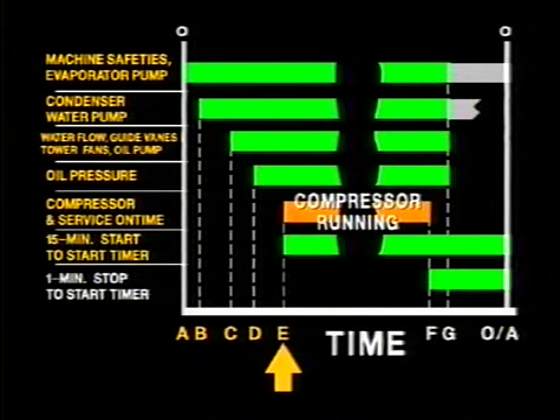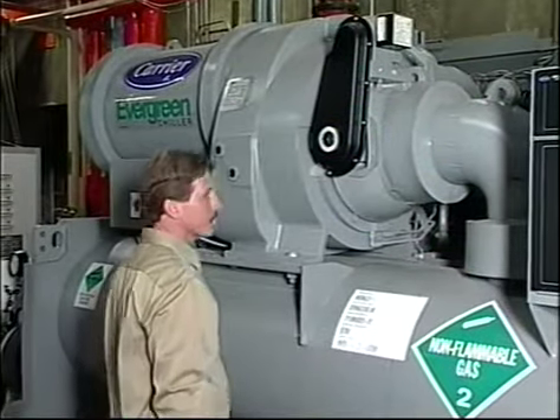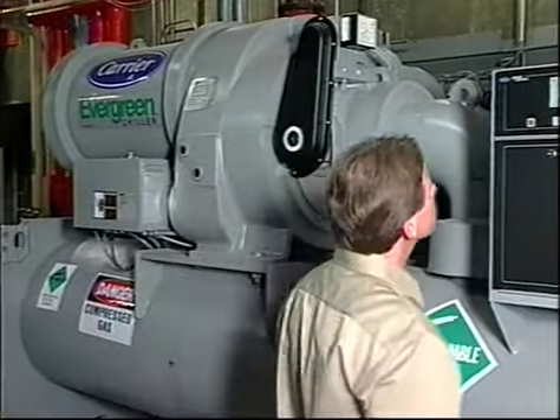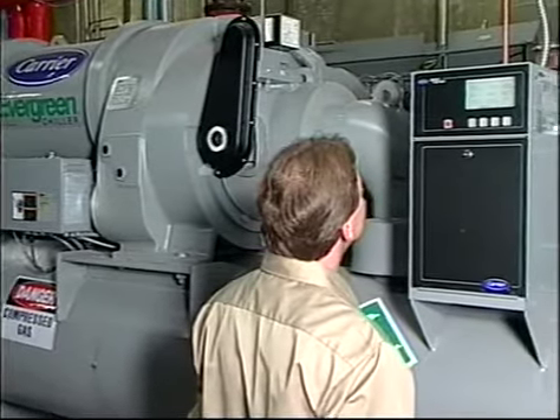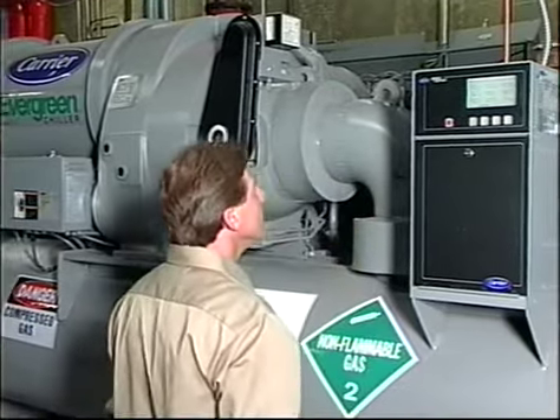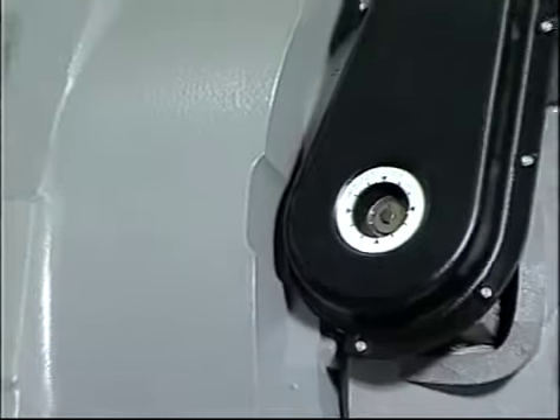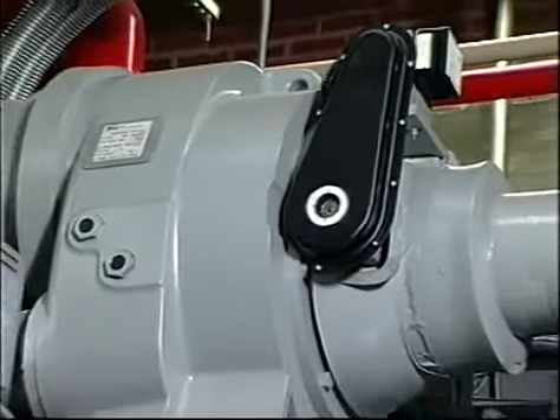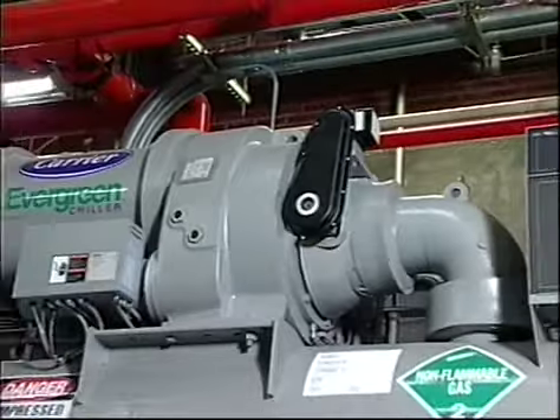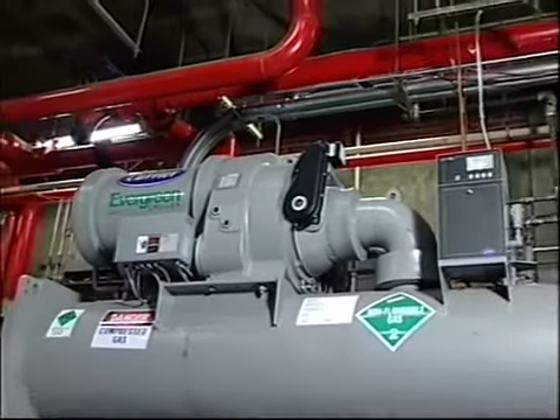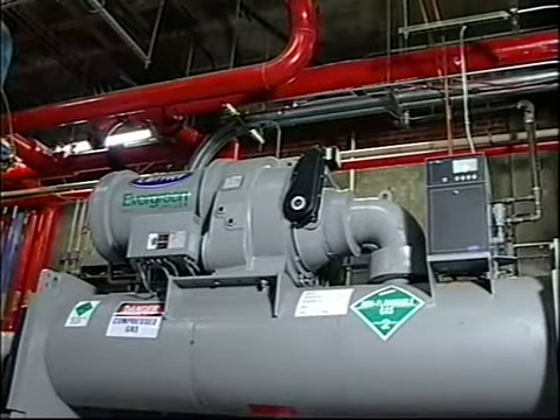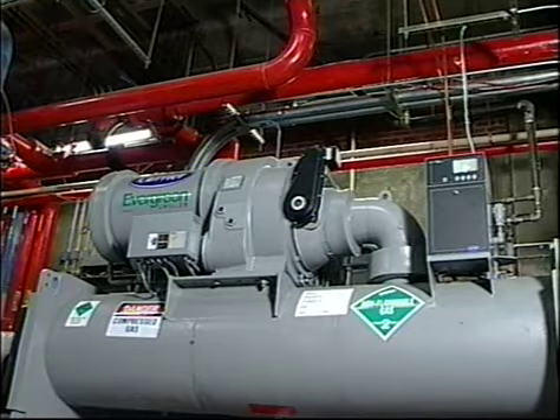After the local key has been pressed, it will take a minute or more for the startup sequence routine to start the compressor. Pay attention to what a normal start sounds like so that you will be better able to detect a problem if anything unusual develops in the future. Once the compressor is running, the controls will operate the inlet guide vanes to provide the proper compressor capacity required by the building, and will manage the operation of optional features such as temperature reset or demand limit.